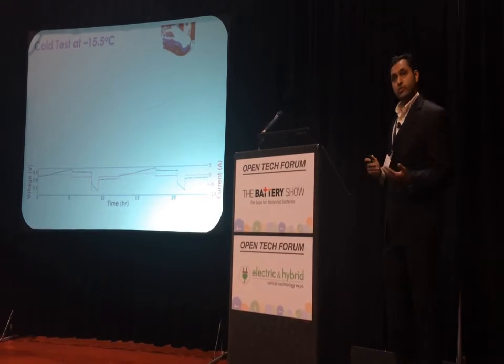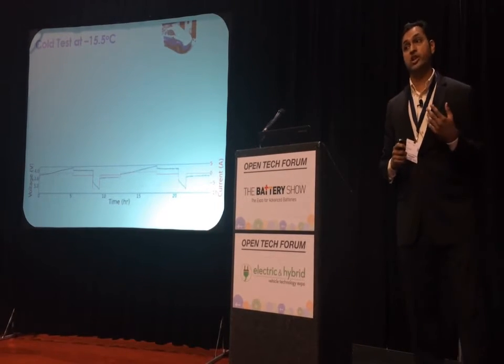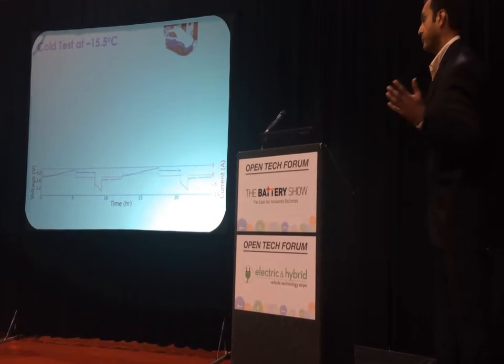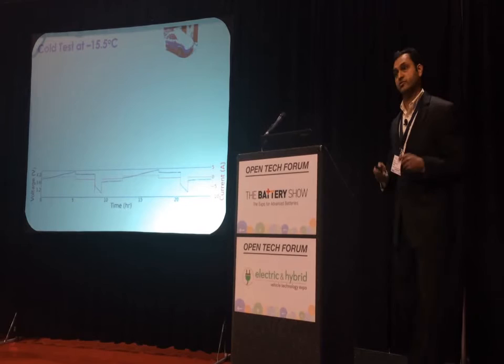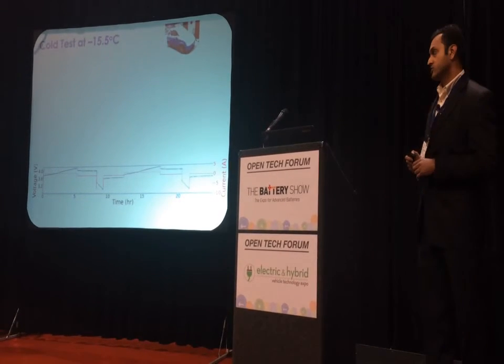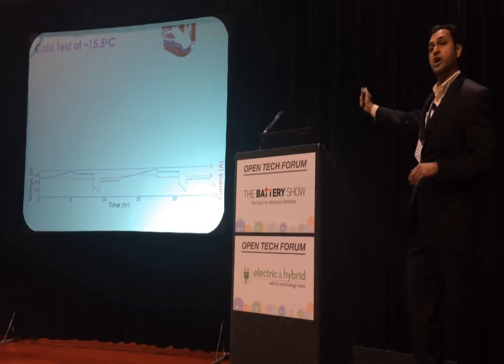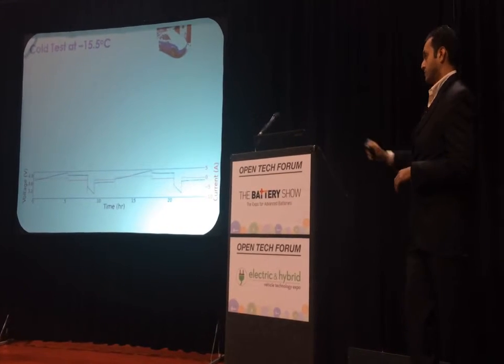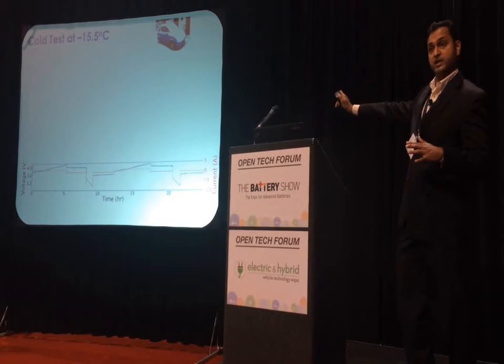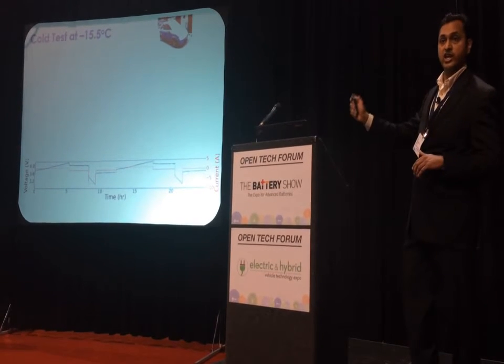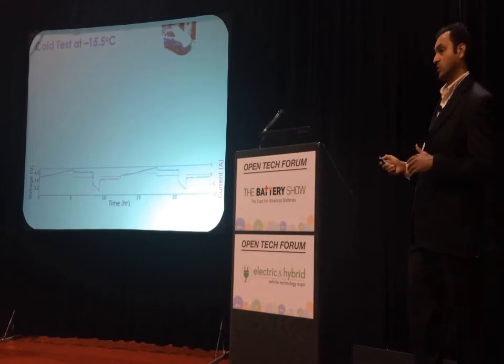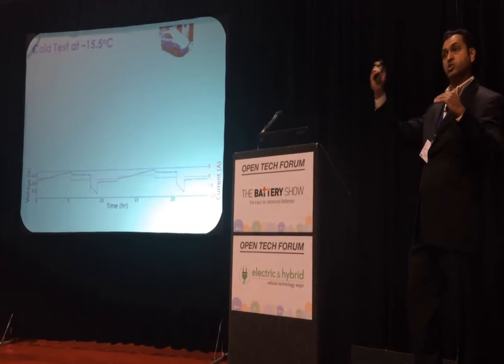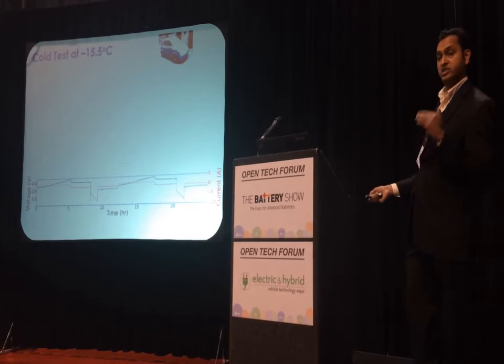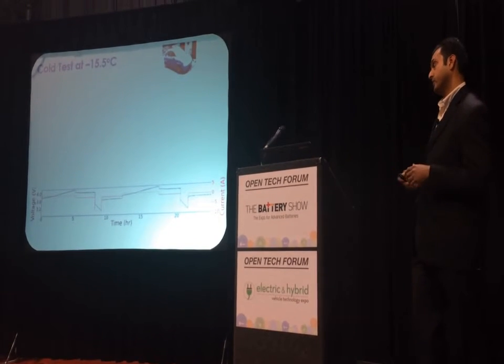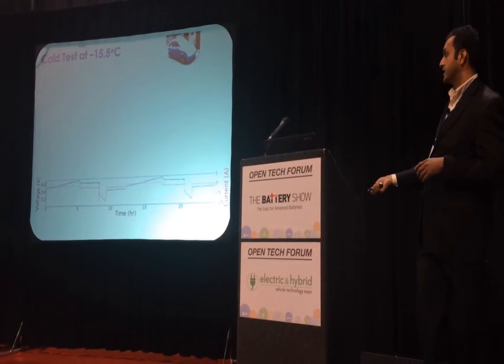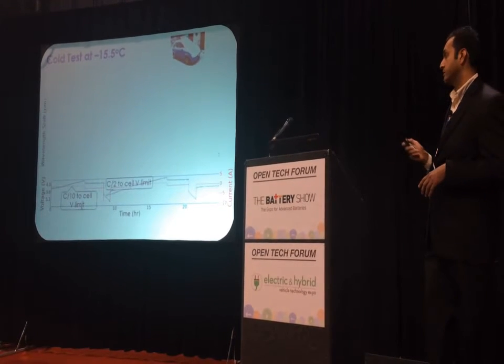One of the known pain points for battery management systems today is their operation in cold temperatures. There have been enough media reports about how EV drivers feel stranded in cold temperatures, so I won't go into too much detail there. But we wanted to put our own sensors through this acid test. Here's an example of a test we did at minus 15 degrees Celsius. We put the cell through its known limits of operational conditions, from the lowest to the highest cell terminal voltage, at the maximum charge and discharge rates recommended by our battery manufacturer LG. The maximum rates in this case were C/10 for charge and C/2 for discharge.